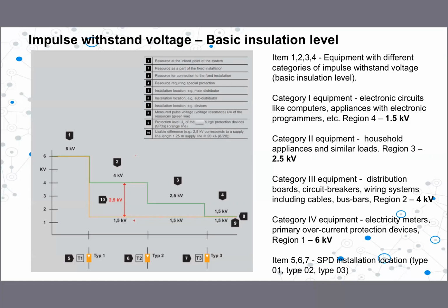Actually, now here in this graph, at the entry point, the insulation level is 6 kV, right? 6 kV. So the surge protection device that we are going to install at this point definitely should be less than 6K. Otherwise, it won't protect the equipment, because the equipment in this region is rated as 6K. So normally we have 6K at the entry point.